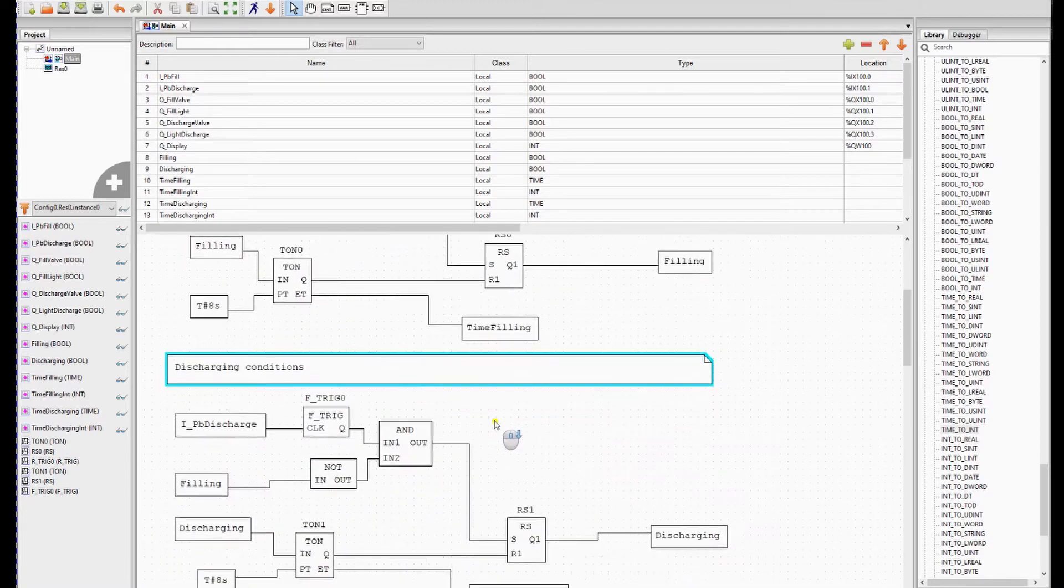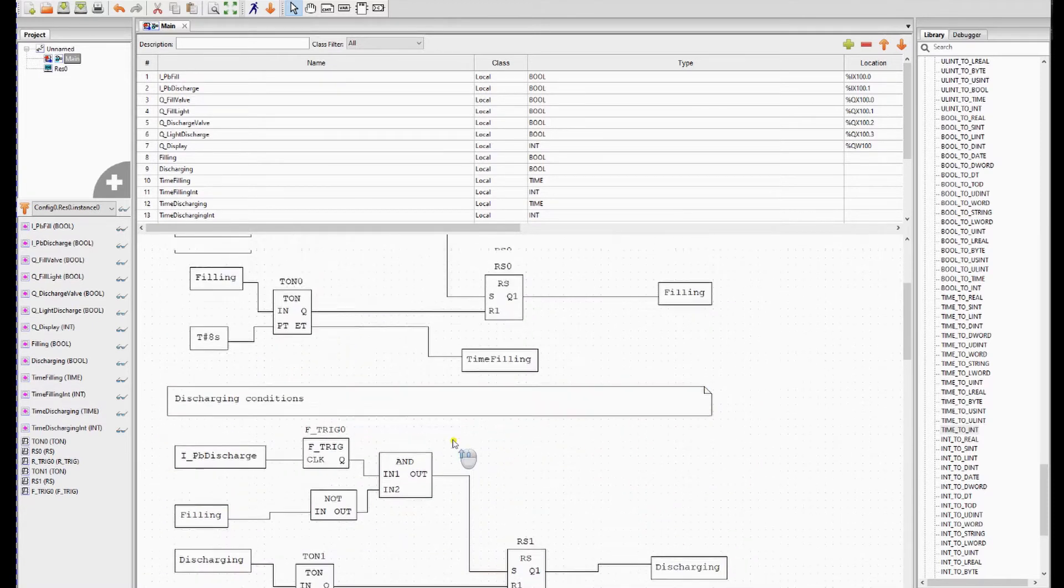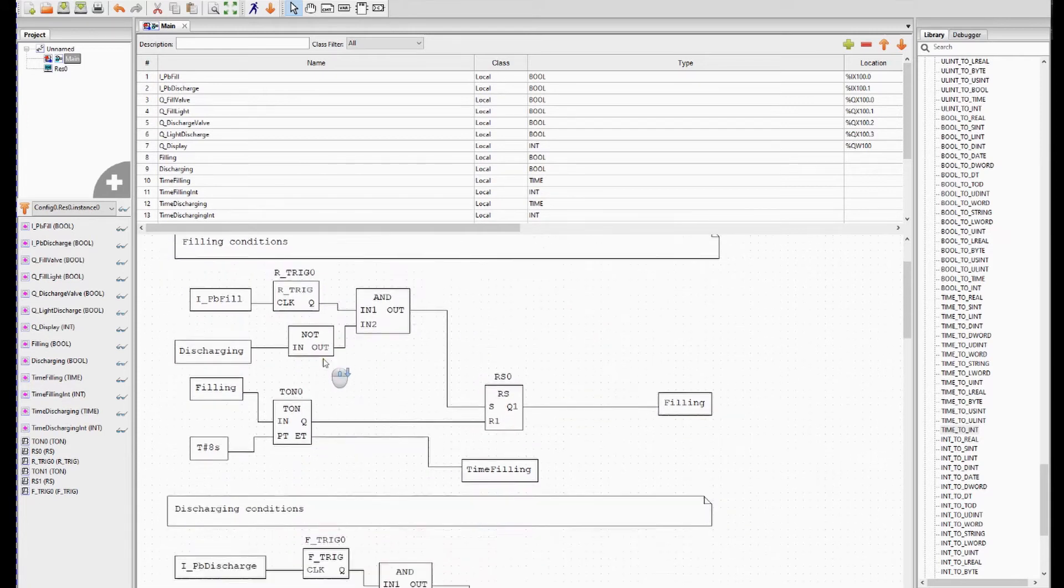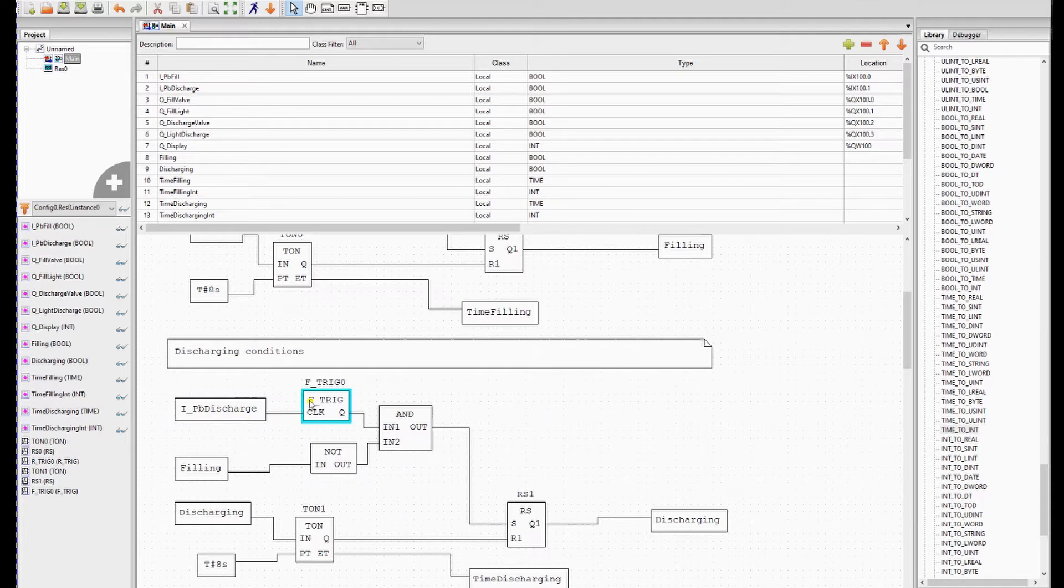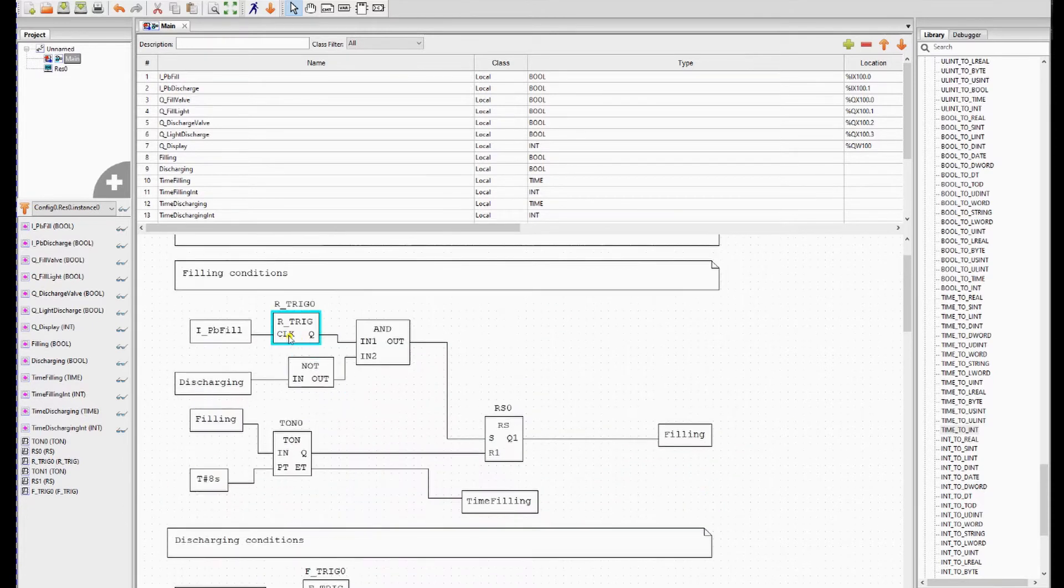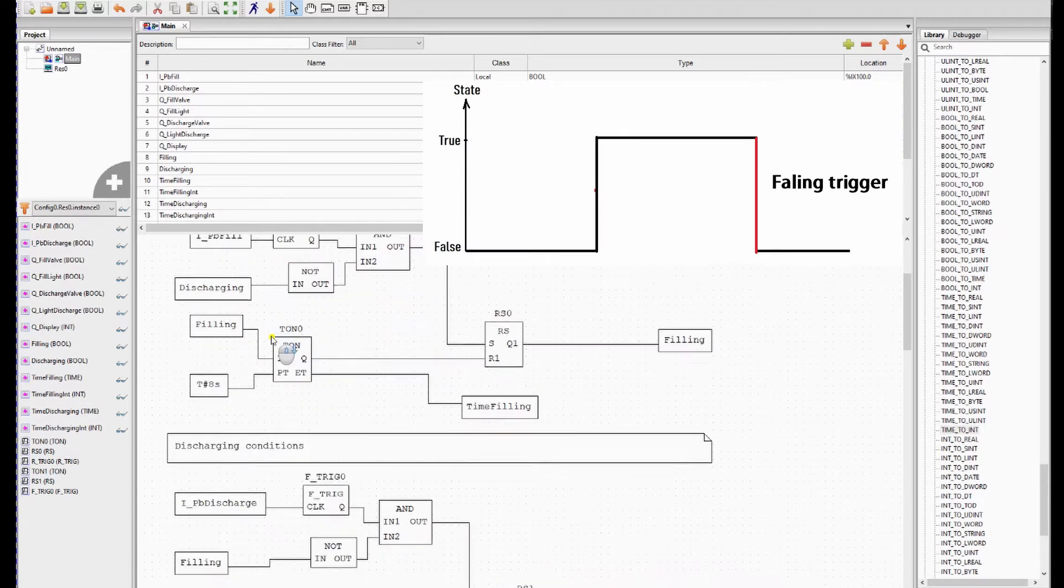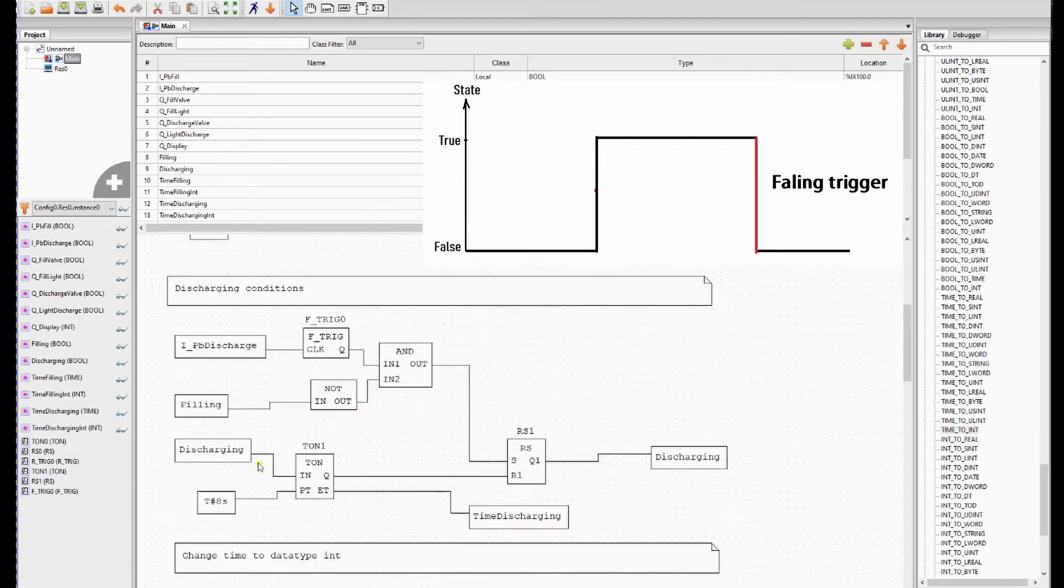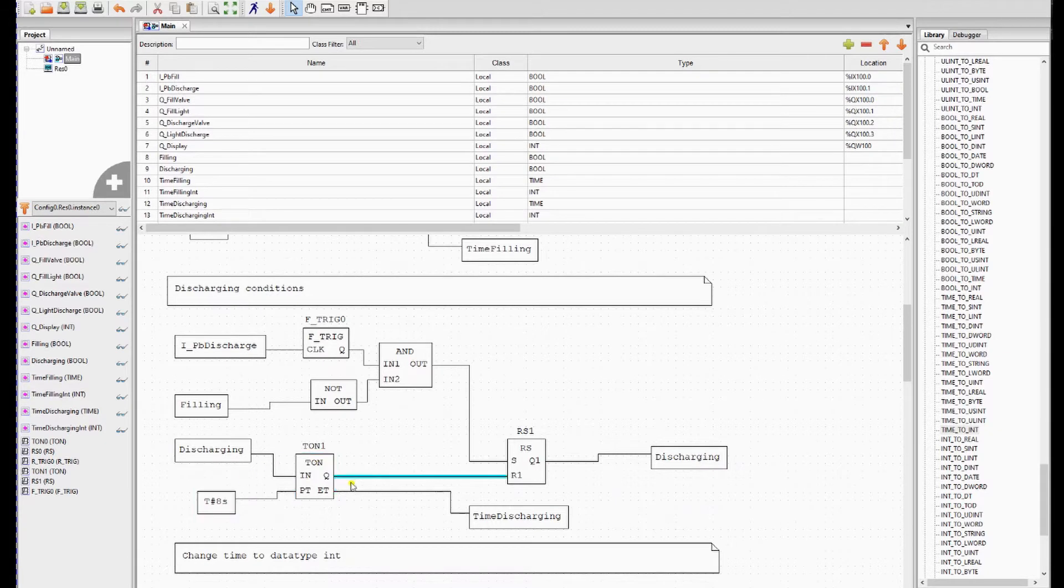Then we have the discharging conditions. They are pretty much the same as the filling conditions but a little bit reversed. So you have to press the discharge button. Please note this is a falling trigger and not a rising trigger like the filling conditions. This is because the button is normally closed. In this case the discharging is only 8 seconds and we remember the time in the variable time discharging.